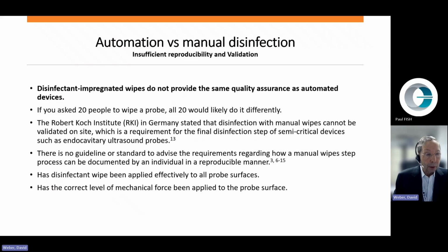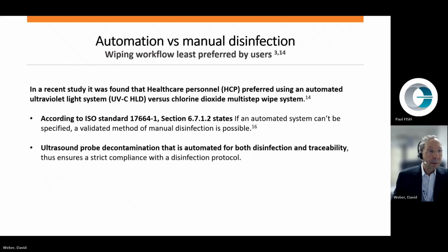Has disinfectant wipe been applied effectively to all probe surfaces? Has the correct level of mechanical force been applied to all probe surfaces? In addition, has the appropriate time been documented? In a recent study, it was found that healthcare personnel preferred using an automated ultraviolet light system, UVC high-level disinfection, versus a chlorine dioxide multi-step wipe system.